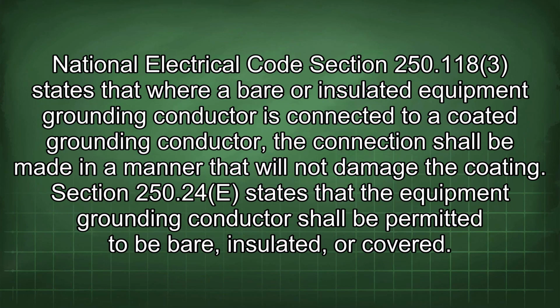National Electrical Code Section 250.118 states that where a bare or insulated equipment grounding conductor is connected to a coated grounding conductor, the connection shall be made in a manner that will not damage the coating. Section 250.24(E) states that the equipment grounding conductor shall be permitted to be bare, insulated, or covered.